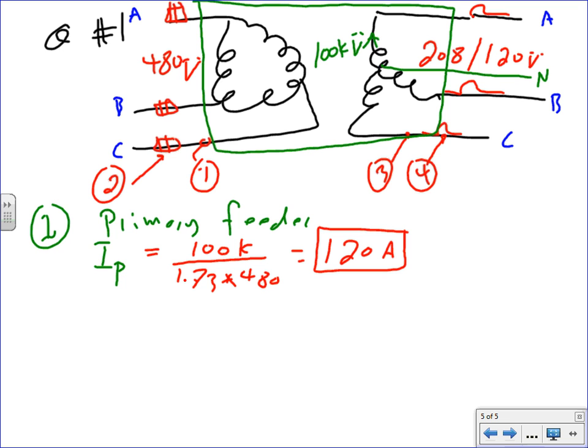But when we do the building, I start with the load, take all the continuous, multiply by 1.25, so you increase the load, then you size your transformer. Now the transformer is accommodating that 1.25, then you size the conductor at 100%. I want to use 1.25 though, just to stay consistent. And why a continuous load? If you read through the code, nothing tells you they have to multiply by 1.25, nothing.